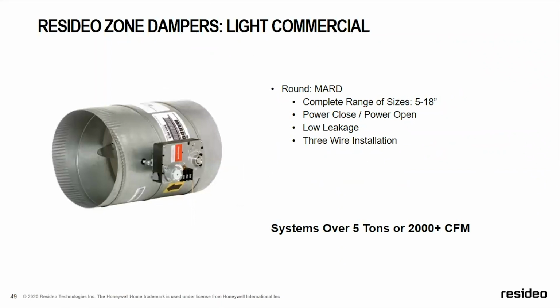MARD, again, this is a light commercial damper. It comes in sizes of 5 to 18 inch. It is power open, power close, low leakage. It is a 3-wire installation. Typically, this is for systems over 5 tons.